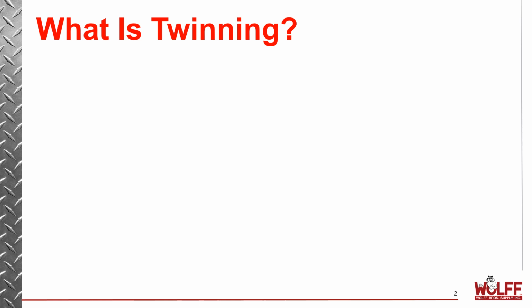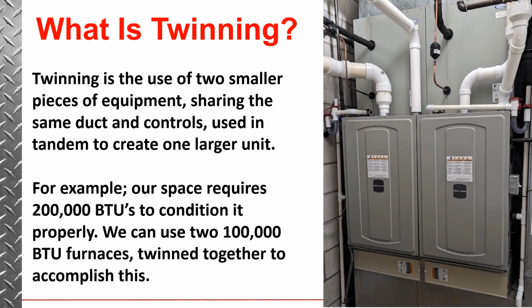So what is twinning? Twinning is the use of two smaller pieces of equipment sharing the same duct and controls used in tandem to create one larger unit. This space requires 200,000 BTUs to condition it properly. So we can actually use two 100,000 BTU furnaces twinned together to accomplish this.